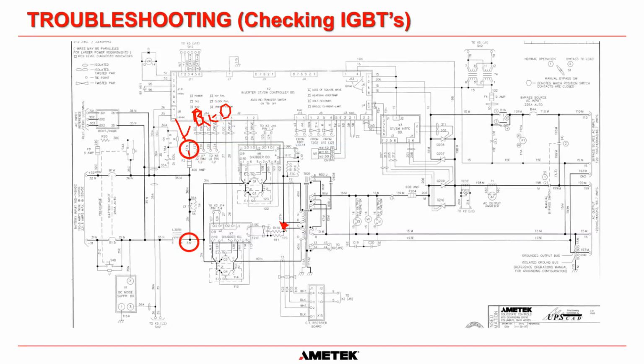It's very important to notice that. The easiest way to get it is on this side of the fuse, and you would have to get the wire number to know which side of the fuse it is. And then we put our other black lead on this terminal here, which is 3N, which is a power connection on the bottom of the IGBTs. If you follow the drawing, these should be open because there's no power going to the system whatsoever. So if you follow this down, you go through the resistance of the transformer, which should be very low indeed. A transformer has very, very low impedance, so it's as if it's a short circuit. And if this is open, then when you measure these 2 points, you should see OL, or at least a very high resistance on your Fluke.